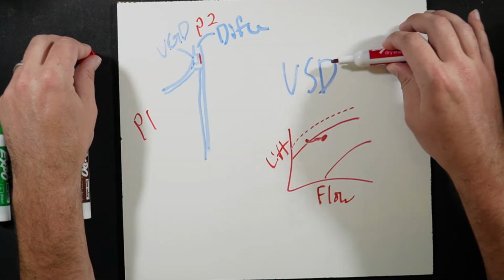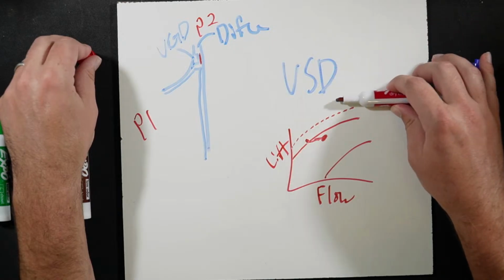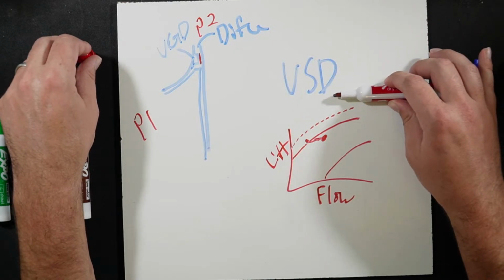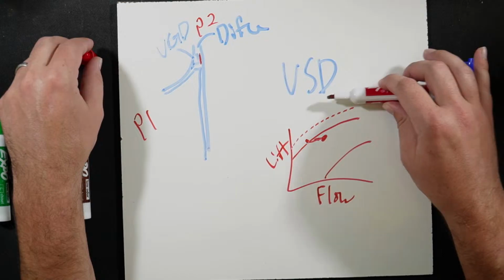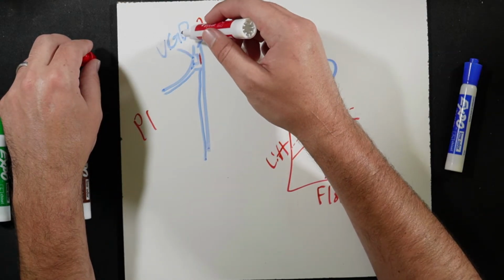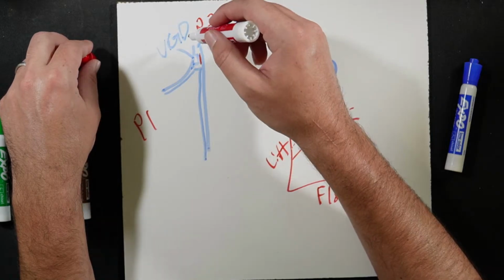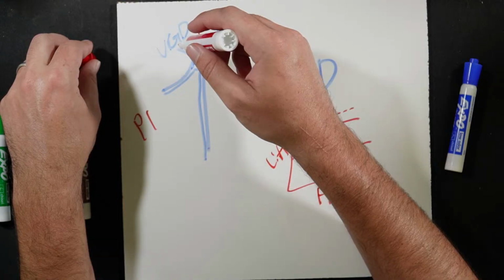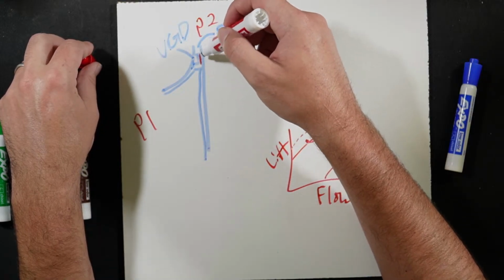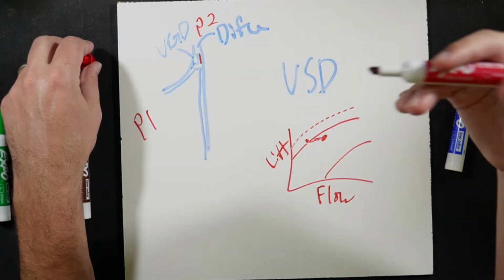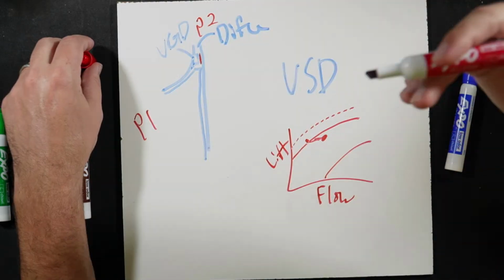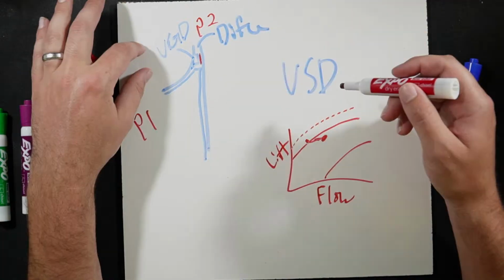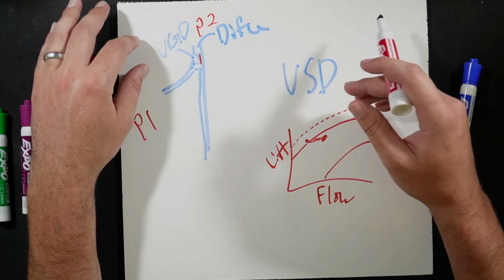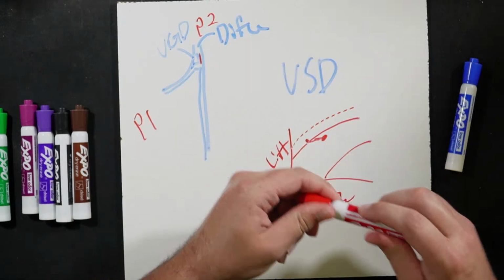But once the compressor actually hits its minimum reference speed that it can get to, then the compressor will intentionally use this VGD, not just for surge protection, but also for load and for unloading the compressor further by restricting this diffuser gap and allowing less total volume through. So it serves a dual function at that point with what it's doing. So yeah, hopefully that helps kind of clear that up a little bit.